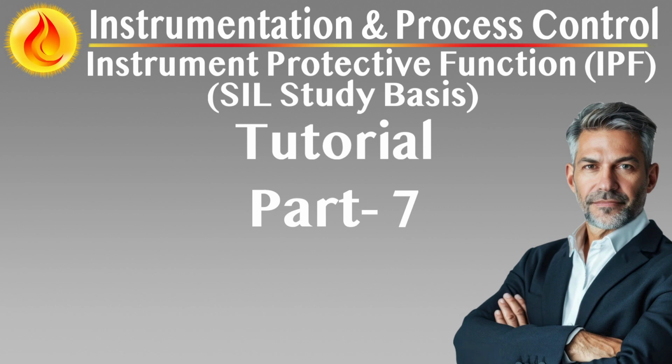HMI visibility and alerting. Operators and engineers must have access to automatic testing status via the HMI or maintenance interface. Alarms should be differentiated from process alarms to avoid misinterpretation. Limitations and complementary measures. Not a replacement for manual proof testing. Automatic testing increases reliability but does not eliminate the need for manual proof tests. Some failure modes, such as mechanical sticking, blockage, or long-term drift, may not be detected without physical verification.